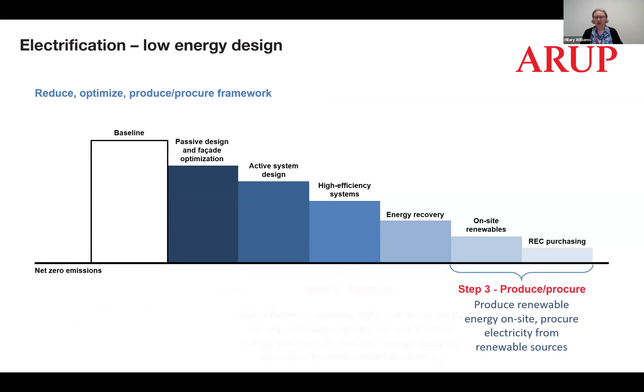So next slide. Within this building, we were given in the sustainability charter a target of making this building all electric, which is quite a challenge for a lab building, which is historically one of the most high energy intensive types of building that you can build. So we had in our toolkit, we decided to go with, given that we have a site to work with, geothermal as our first stage of design to do the majority of the heating and the cooling demand for the building. And then we augmented that with a second stage and a third stage, both in heating and in cooling, of air source technologies such as air source heat pumps, air-cooled chillers, and then for very small proportions of the demand of the building, electric boilers.